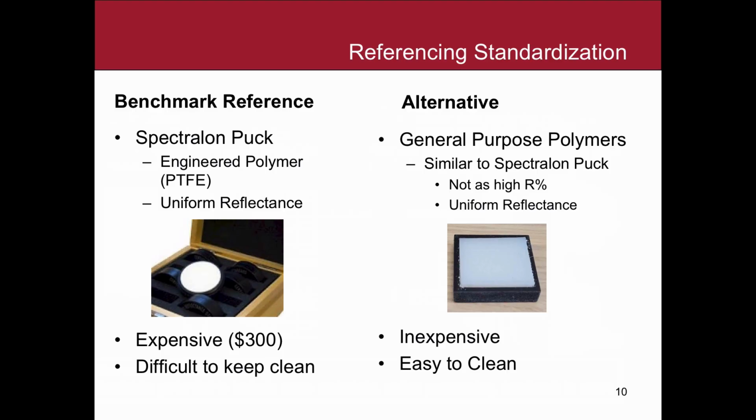Another important aspect of our device is our referencing and standardization technique. With most medical imaging devices, there's typically a reference standard that's used with it due to the LEDs being variable in intensities. A benchmark reference for this is a Spectralon puck, which is usually made from engineered polymer called PTFE, due to its ability to have uniform reflectance and high reflectivity. But this is quite expensive at approximately $300, and it's difficult to keep clean.